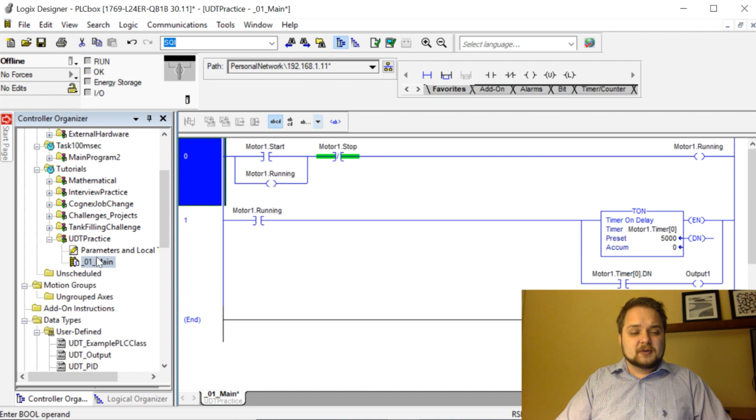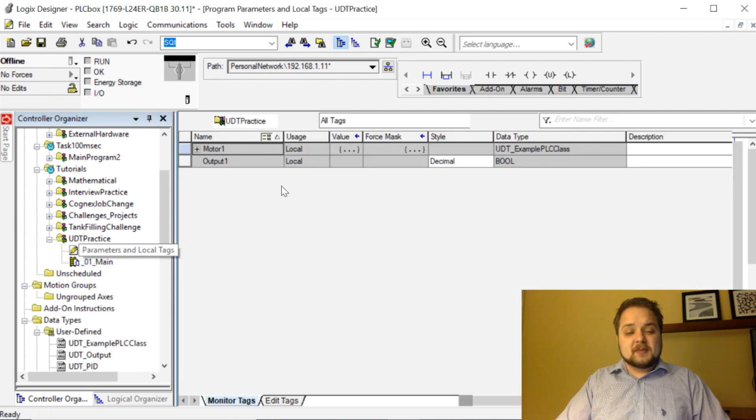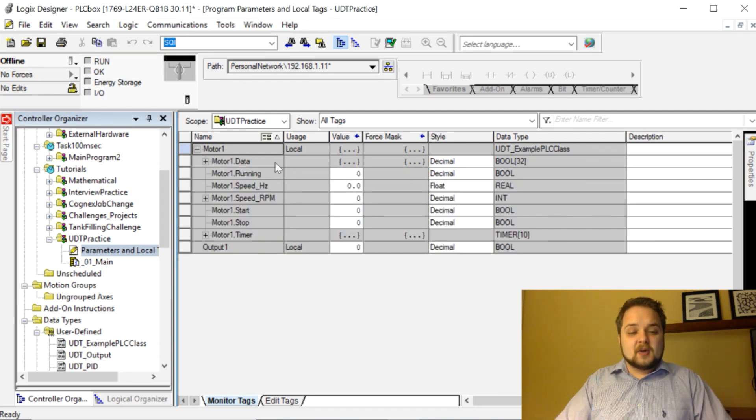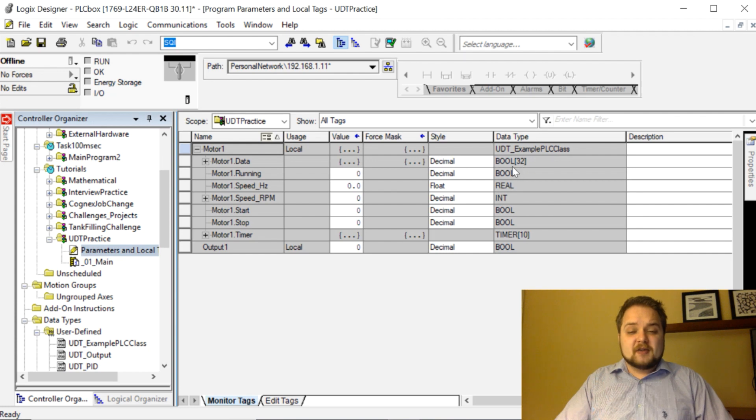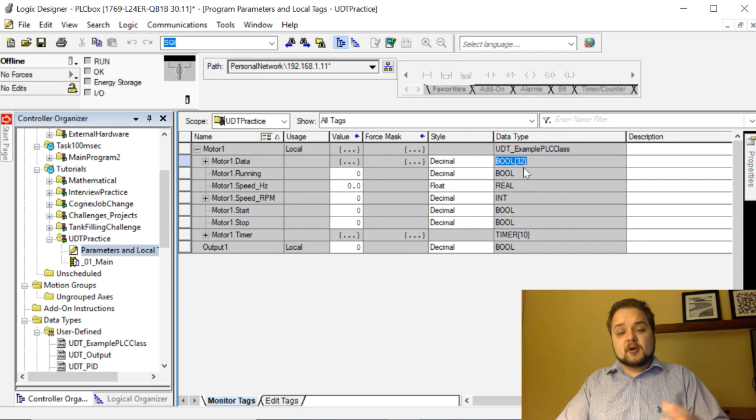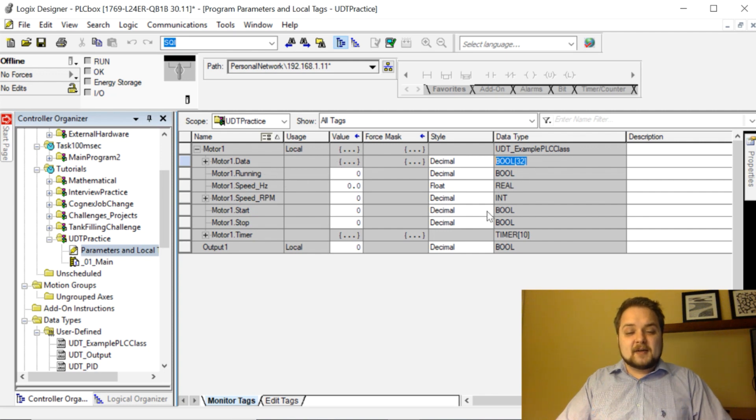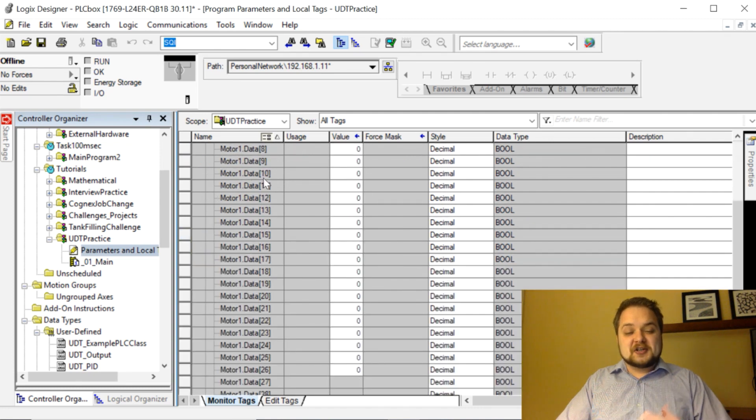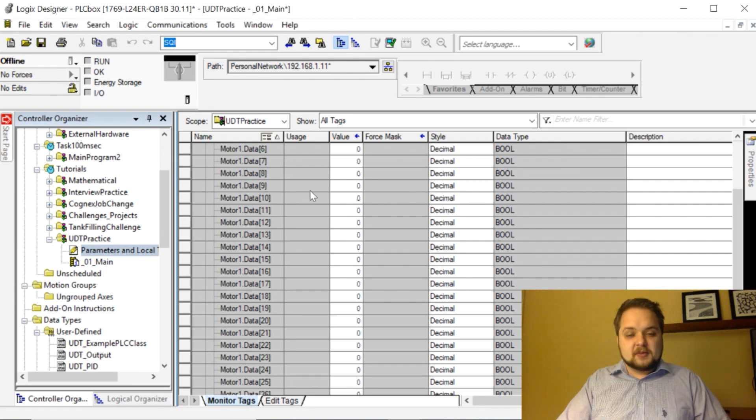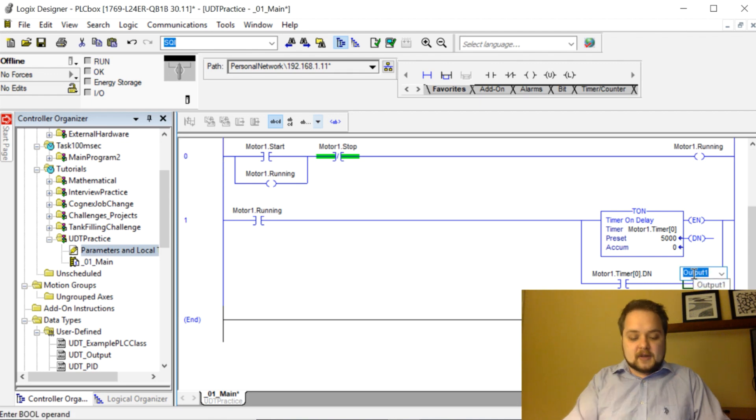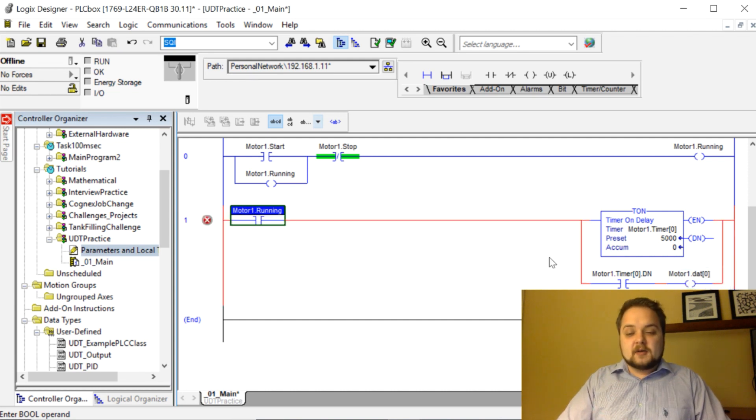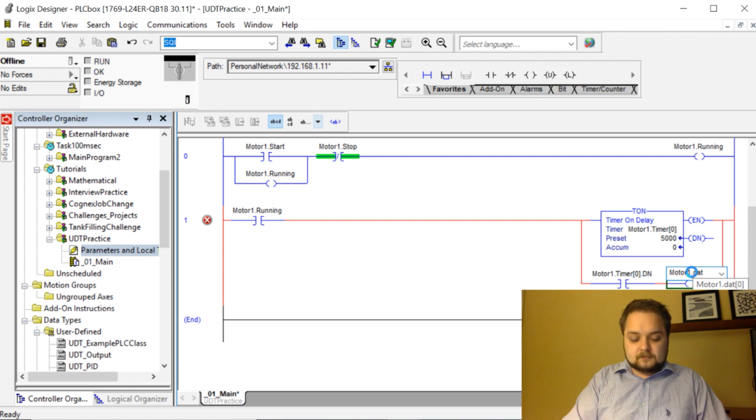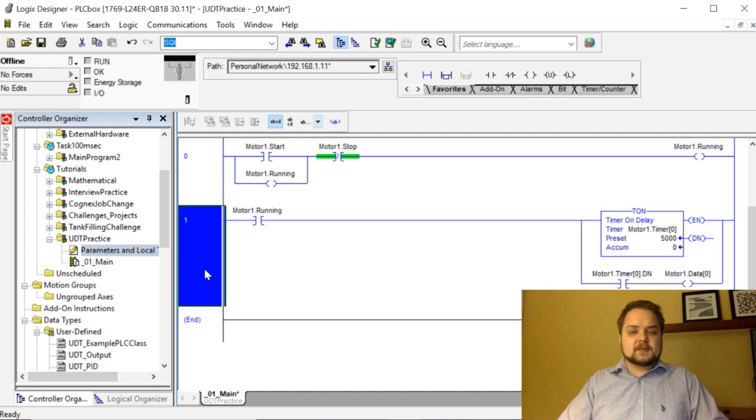This is a very simple example but it illustrates very well what's going on here. We didn't have to create individual booleans for each one of those start stop buttons, running not running, timers, all kinds of different stuff. If we go back into our local tags you will notice that the motor one type that we've created is a self-contained block and once we expand that block as you can see we have all the tags that we've talked about. We have the booleans, the reals, the integers, and of course the arrays. The arrays are specified by their size, so this means that there's 32 booleans within this data array and there's going to be 10 timers within this time array. If you hit this little plus here you can expand the array and look at each and every boolean. Of course you can call them by this data, so for example here if we were to tie in instead of going to this output one we could have said that motor one dot data zero is actually the tag that we want to activate.